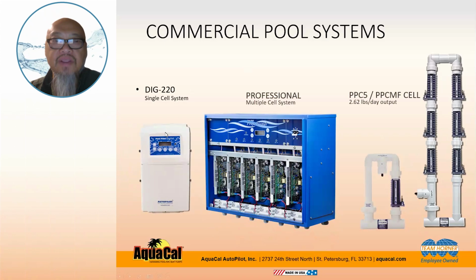So when we look at what we currently offer, the DIG 220, which is a single cell system that operates with this manifold assembly, and the AutoPilot Professional, which operates with this multiple cell manifold assembly, we can see on here that the single cell systems, or the cells, will currently produce 2.62 pounds per day of output per cell. All right, which is quite a bit of chlorine generation on a single cell application. With the multiple cell manifold, the AutoPilot Professional, for each cell that's in the manifold, we'll have a power center attached with it also. Now, if you're familiar with this, we can do quite a bit of volume of water with a 6-cell system, which puts out over 15 pounds per day of chlorine production. That's a pretty big pool that it'll be able to handle.